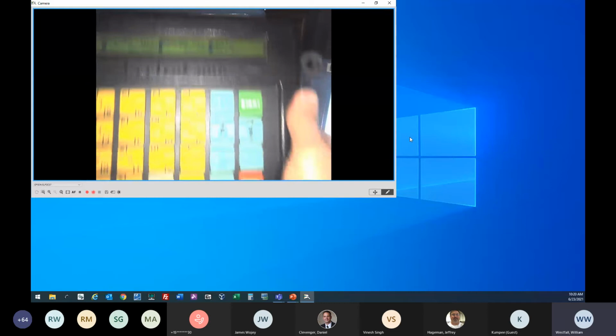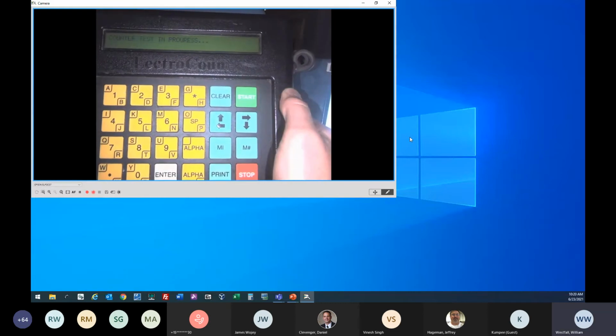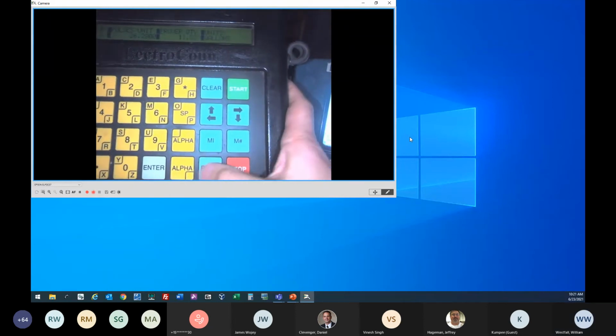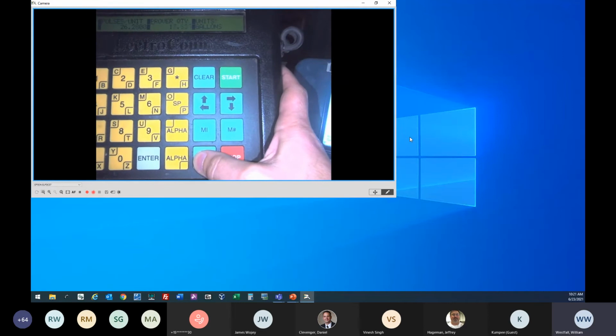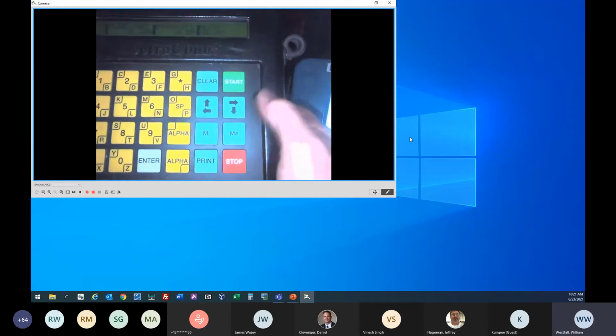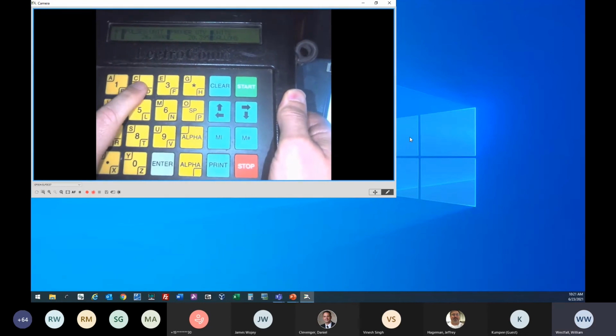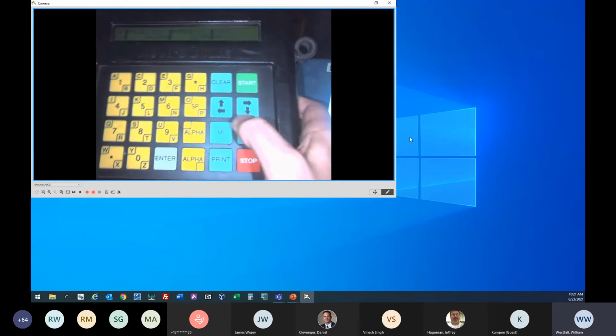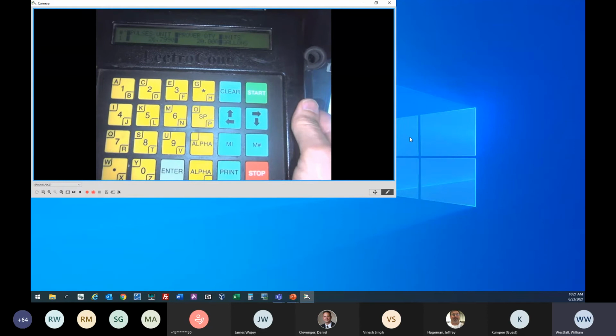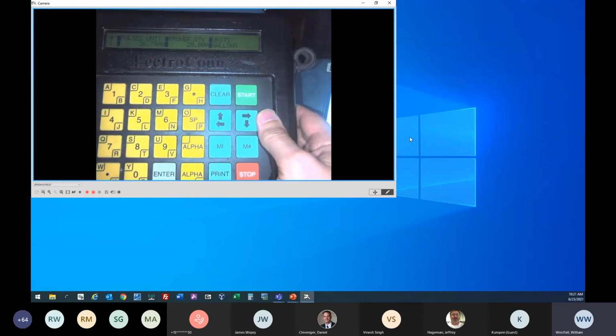So if you wanted to make another run, all you would have to do is hit the start key. We get a counter test, and we're delivering our prover quantity. When we're ready to stop, or when the prover is full, we hit print to end the delivery. And we've got a prover quantity there. We would hit the enter key and say, okay, we have a prover quantity of 20 gallons. Hit enter, and now our pulses per unit has changed again. So that's how you would go through using the keypad on the LCR2 itself.